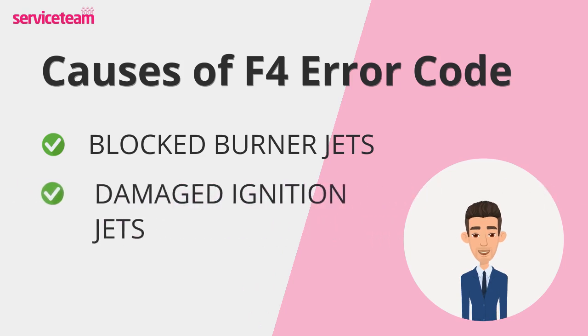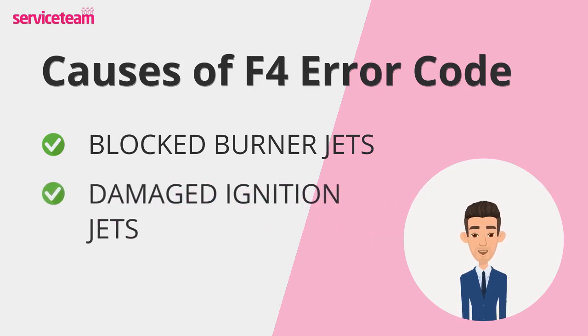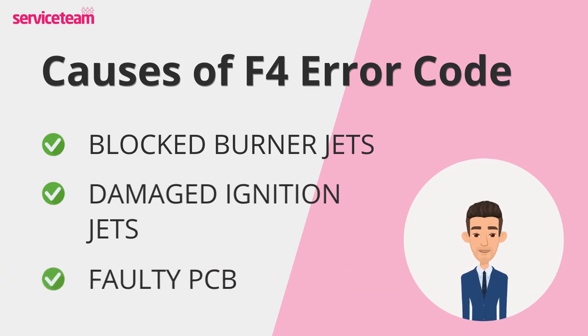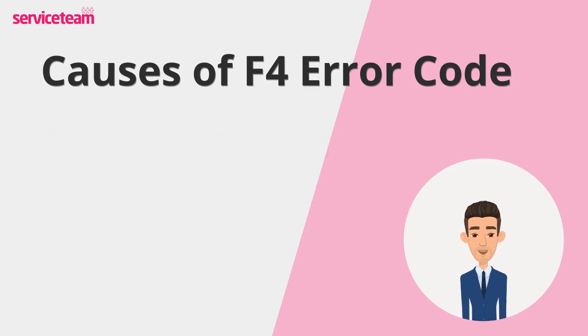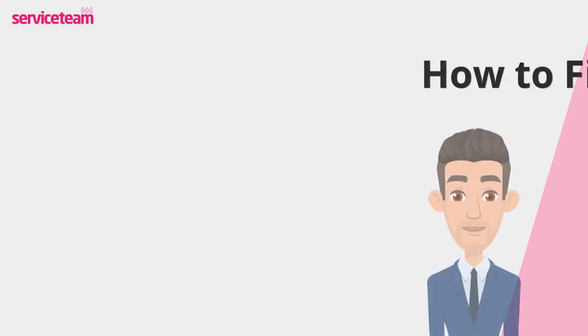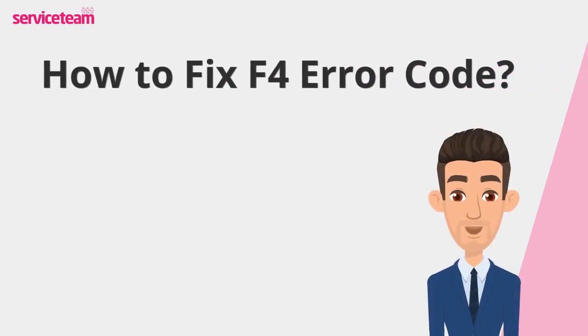Your boiler also relies on the ignition lead to spark the gas and start the flame. If this lead is damaged, the boiler simply won't ignite. And finally, the PCB, or printed circuit board. This is like the brain of your boiler. If it's malfunctioning, it might misread signals from various components, leading to the F4 fault. Let's find out how to fix the F4 error code.